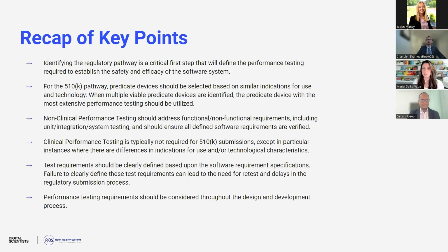For lower risk class devices that fall under the basic documentation level in accordance with FDA software guidance, for unit integration testing, you typically just have to provide plans as far as how you perform your unit integration testing, while having to provide plans, protocols, and reports with raw data for the system testing. For higher risk devices that are subject to enhanced documentation level requirements from FDA, you need to have plans, protocols, and reports for unit, integration, and system level testing.